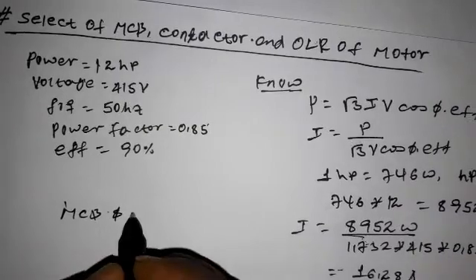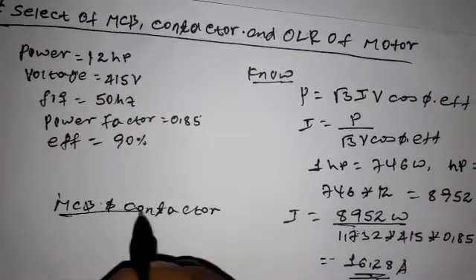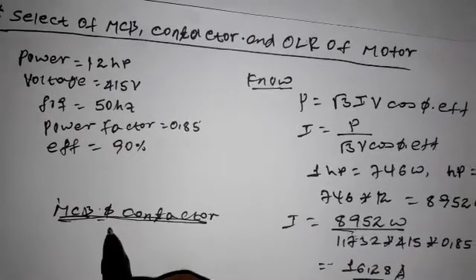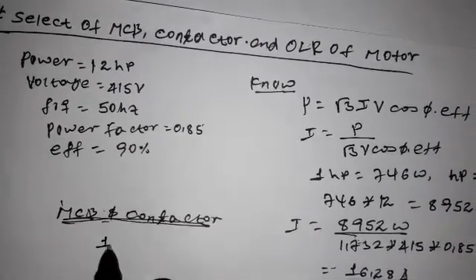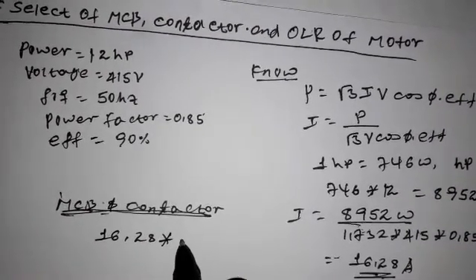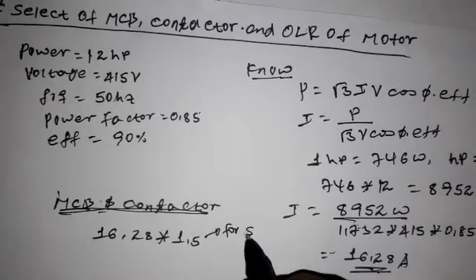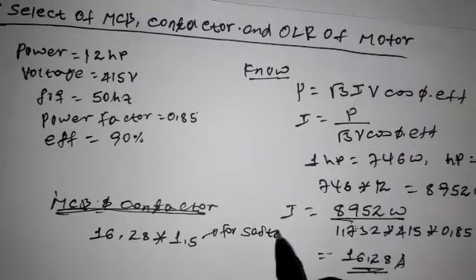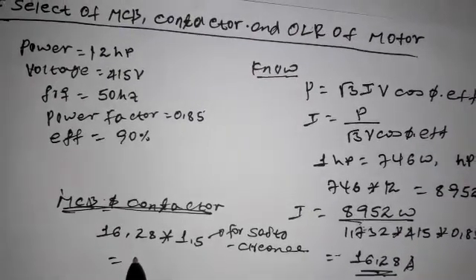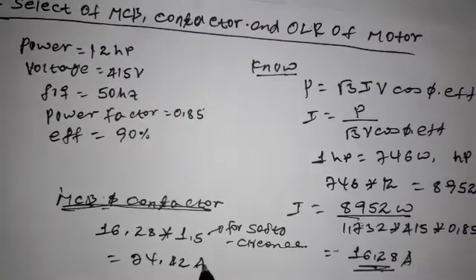Contactor and breaker, MCB and contactor, it is times 1.5. 1.5 means it is for clearance, it is safety. Clearance of current is too much. Then, 24.42 Ampere.